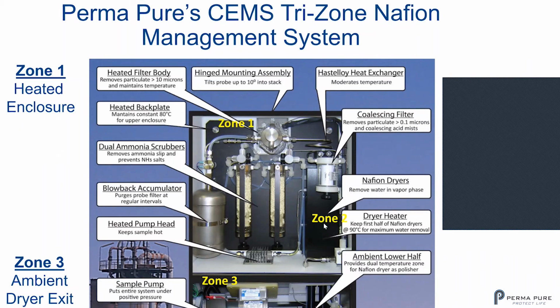So that's zone 2. Zone 1 is the whole area that prepares the sample gas for the dryer. Zone 2 is the portion of the dryer that is heated, that removes the bulk of the water. Zone 3 is our ambient lower half. That's where the sample gas in the dryer is chilled and cooled primarily by the purge gas. The whole area in zone 3 is cool, primarily because there you have your computers, your PLC, your heatless dryer, your sample pump, anything else that needs to run at a lower temperature for high reliability. That's how our sample systems work.